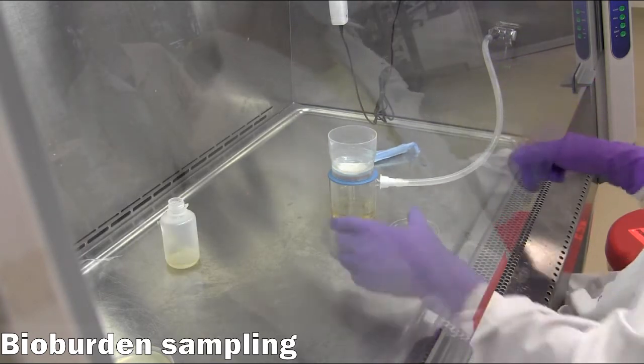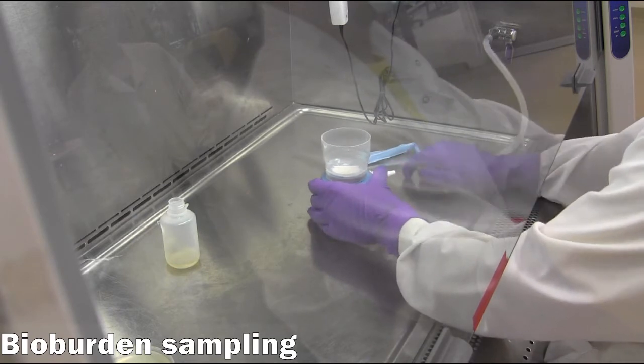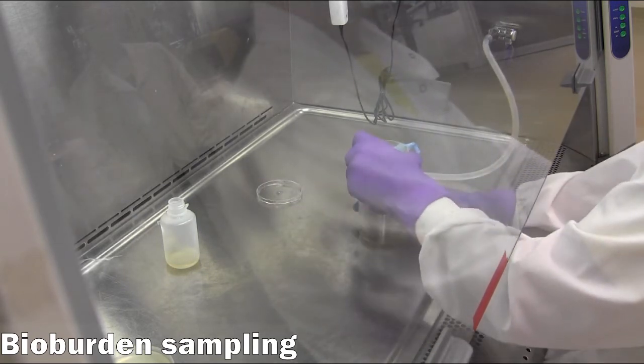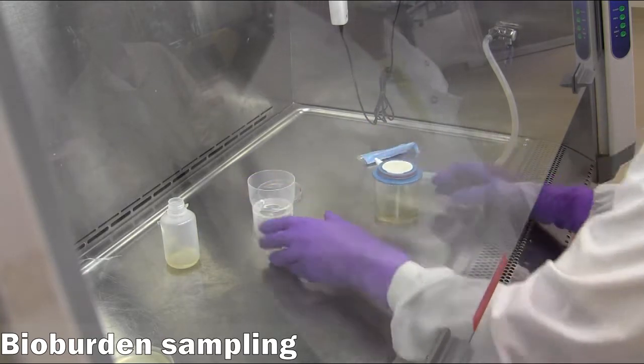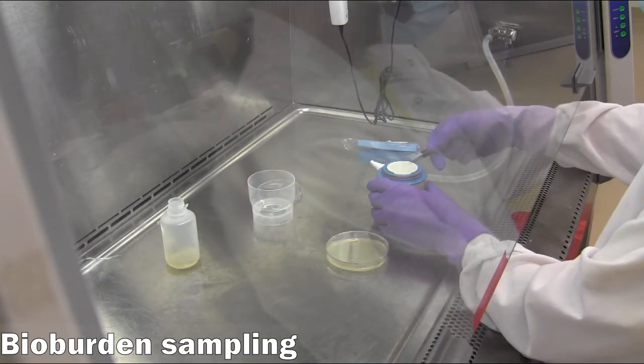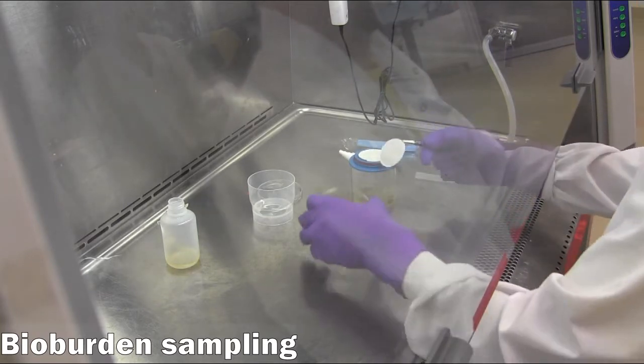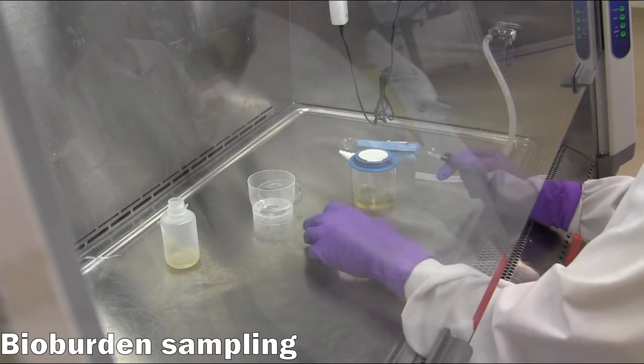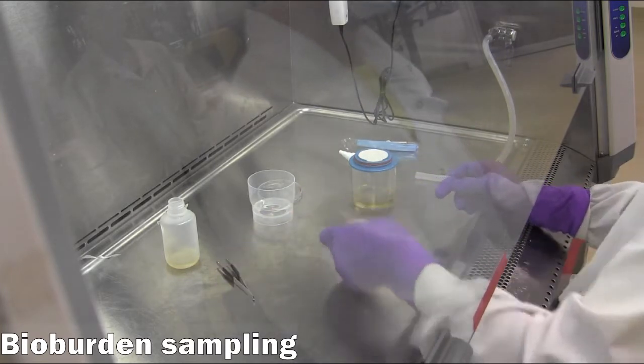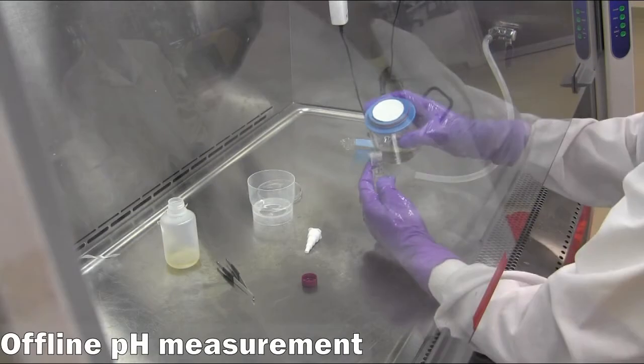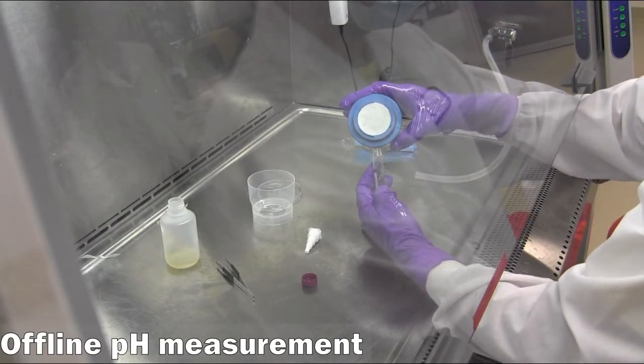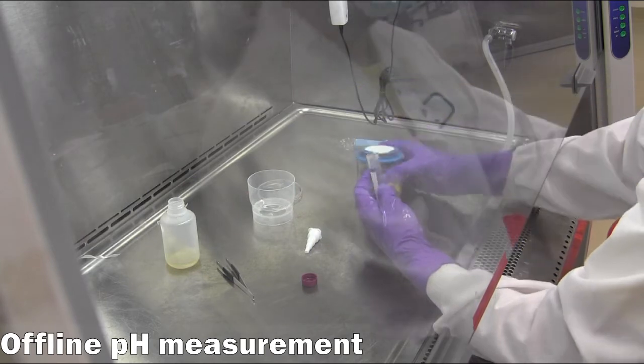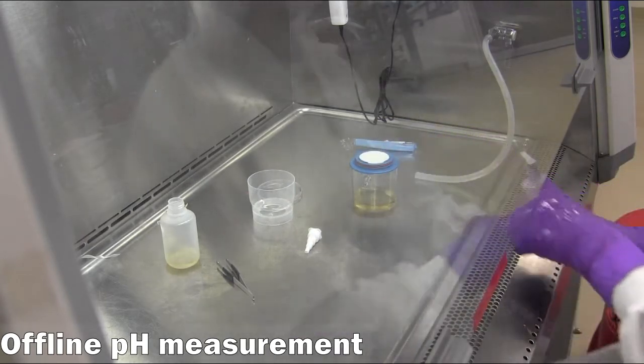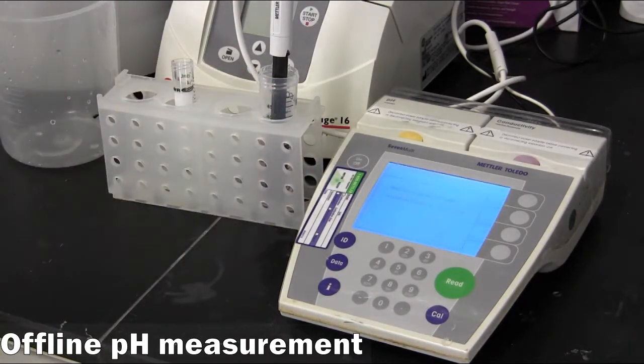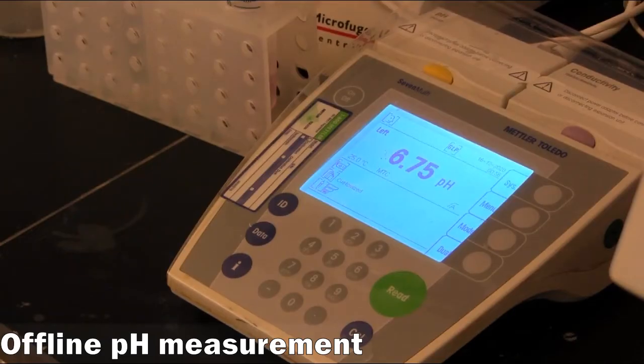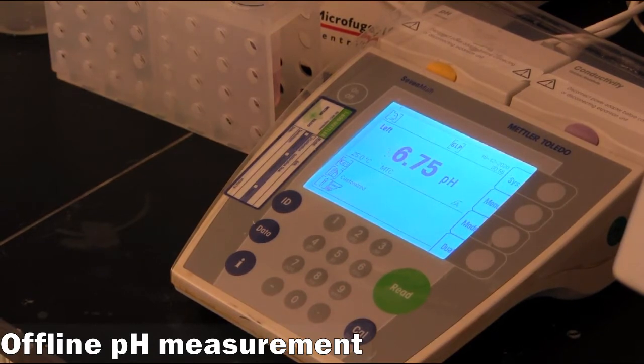Once the solution has been filtered, remove the lid from around the filter and use sterile tweezers to transfer the filter paper to a petri dish face down. Incubate the petri dish at 37 degrees C. The flow through from the bioburden sample can be used for an offline pH measurement. Compare the benchtop pH meter result with the online pH reading on the bioreactor. If there is a significant difference, recalibrate the bioreactor pH probe.